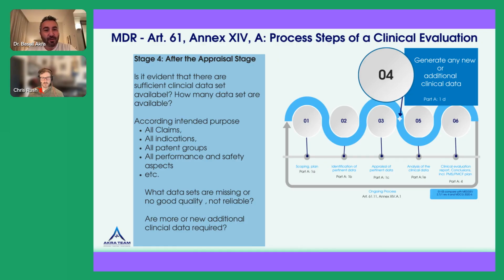So the claim should be connected with a clinical reason, and you might have a patient population which has limited ability to get a device, and they might be treated one or two times per year. No one will be asking you for such a patient population to have clinical data before you get to the market. You can justify why those patients will not be studied, but will perhaps be covered by your post-market activities, and you're going to collect data.